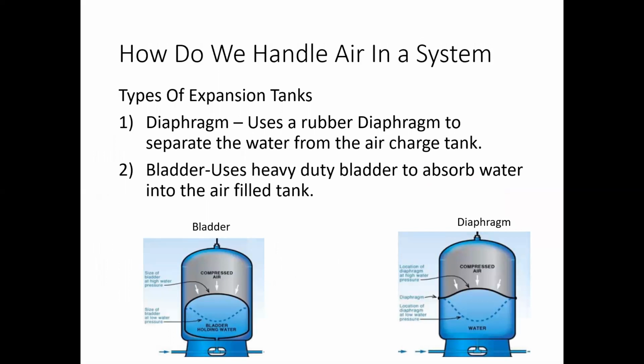Now we have two types of expansion tanks that are commonly used, right? Technically there could be three, because you have the old school compression tanks, but nowadays we're seeing one of two types. On larger systems, you're going to see a bladder tank, which uses a heavy duty bladder to absorb water into the tank. On the smaller systems, you're going to see a rubber diaphragm tank, and both have their pros and cons. Primarily, the bladder tank is going to be more money, but it's a more efficient tank. You can change the bladder down the road, whereas the diaphragm tank kind of looks like a Snapple cap on the inside, where you reverse that half Snapple cap and it makes that popping noise. It pushes back and then it clips back.